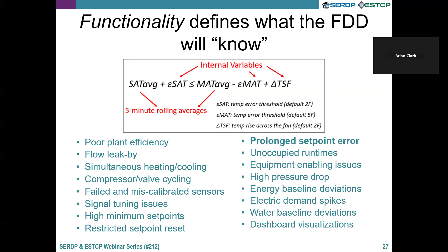You're taking average conditions, you're adding some kind of reasonable thresholds for things like, in this case, fan heat. And there's some internal constants that have to be mapped out there, because we know that there's no perfect temperature sensor. And as we start running through these equations, we don't want to have more nuisance alarms for our building staff. So you could get 40 of these from certain vendors or platforms. You could get 4,000. So what we wanted to look for in DoD was probably not the Cadillac of fault conditions, but we wanted to be able to identify high priority ones that seem to be supported by most FDD providers. We've got a list of that to pull from kind of a la carte in some of our template information.